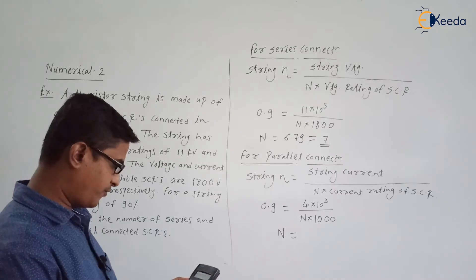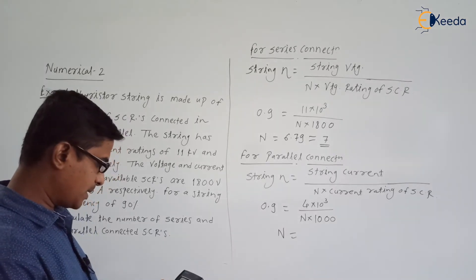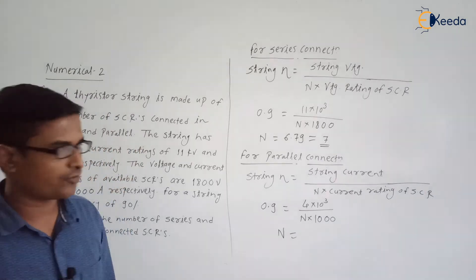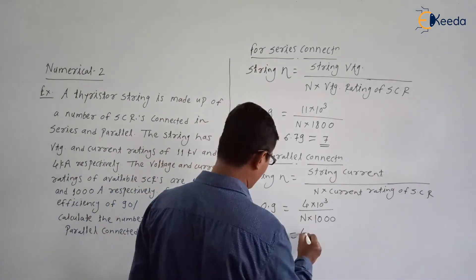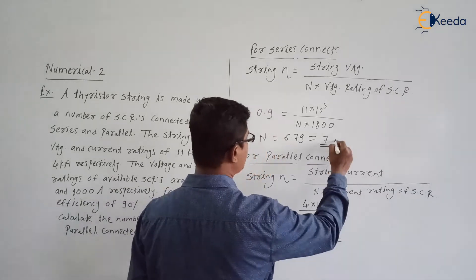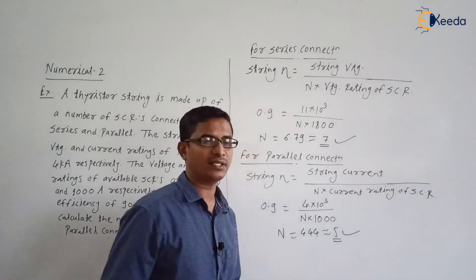We can find the number of SCRs required to be connected in parallel. It is 4000 divided by 1000 divided by 0.9. So it is 4.44 means roughly 5. So we need to connect 5 SCRs in parallel and 7 SCRs in series. Are you getting the point?